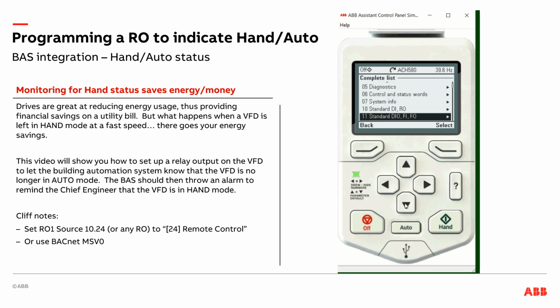So the relay outputs are right here. You can see standard DI for digital inputs and relay outputs. So I'm going to go into my relay outputs here. We start with the digital inputs. I'm going to scroll past those quickly, all 6 of my digital inputs. And now I'm going to go to my relay output. So I can see the status of my relays right here in parameter 10.21.